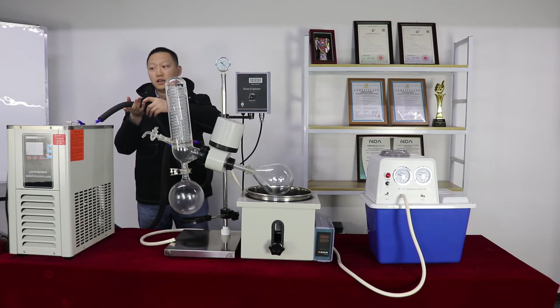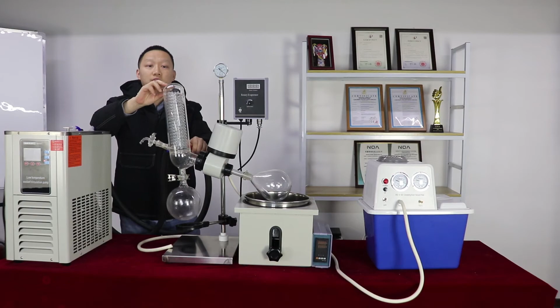This is the whole system. Make sure, for some other types of condenser, this one port is on the upper side, not both of them downstream. If one of them is upper and one is lower, make sure the lower one connects with the outlet of the coolant chiller. This is very important: the outlet of the coolant chiller always connects with the lower part of the condenser.